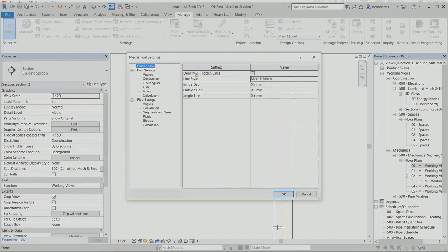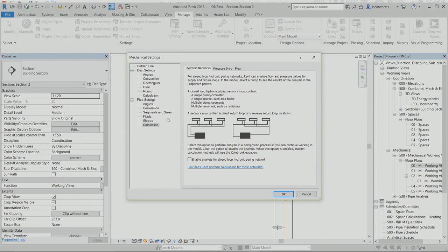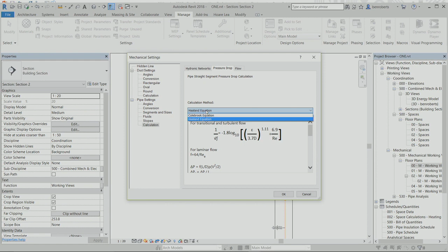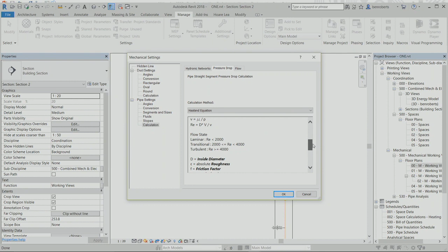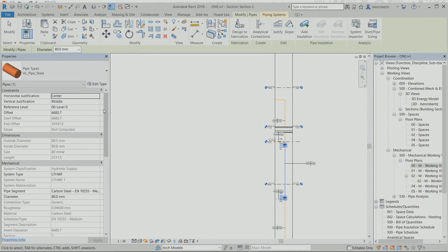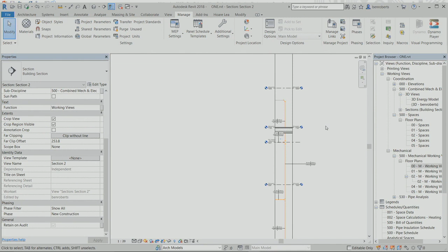That is based on, if you go to Manage, MEP Settings, Mechanical Settings, you see under both duct and pipe, but as we're looking at pipes, there's this calculation feature. And you can choose which calculation method you want to use. In the UK, CIBSE recommends the Haaland equation, and that's written out there. So you can see it's not a black box. You can see what equation it's doing. That's the pressure drop that it's calculating. So when you click on a pipe, here we go. That's the pressure drop that we're getting. So pretty good.